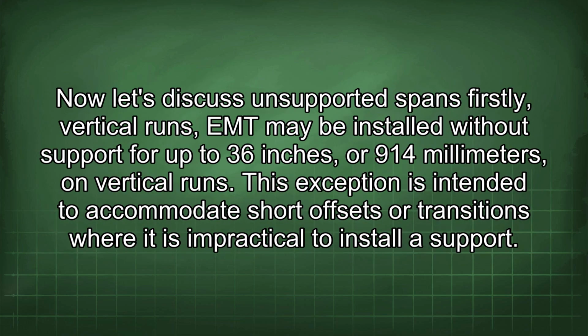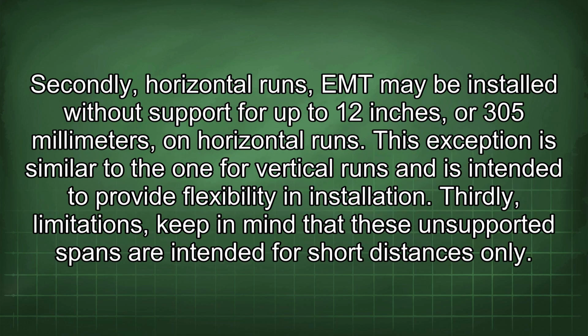Now let's discuss unsupported spans. Firstly, vertical runs. EMT may be installed without support for up to 36 inches, or 914 millimeters, on vertical runs. This exception is intended to accommodate short offsets or transitions where it is impractical to install a support. Secondly, horizontal runs. EMT may be installed without support for up to 12 inches, or 305 millimeters, on horizontal runs. This exception is similar to the one for vertical runs and is intended to provide flexibility in installation. Thirdly, limitations. Keep in mind that these unsupported spans are intended for short distances only.